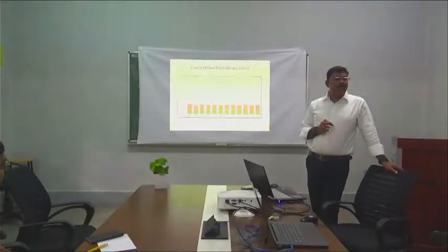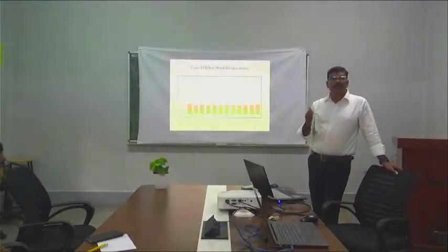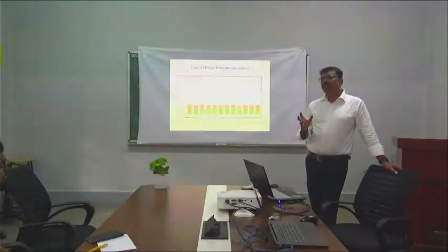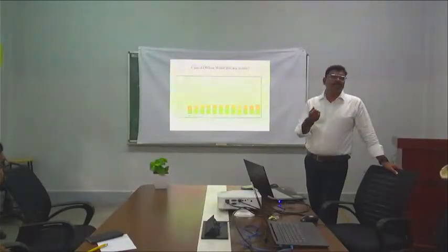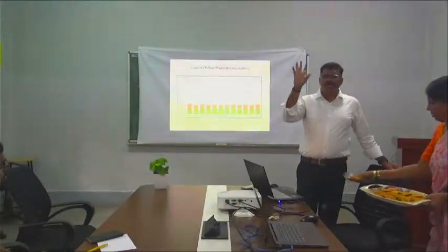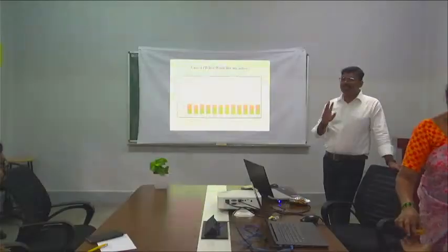Excess power can be between 5 to 10%. It is based on the configuration you select. It is based on the reliability you consider. All those matter. But what about unmet electricity? Somewhere in 365 days, sometimes there is no electricity in a microgrid. That is called unmet electricity.